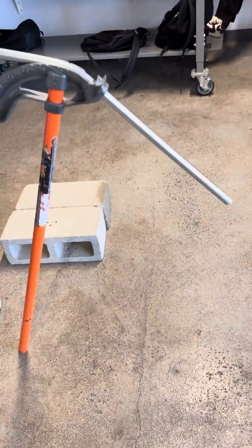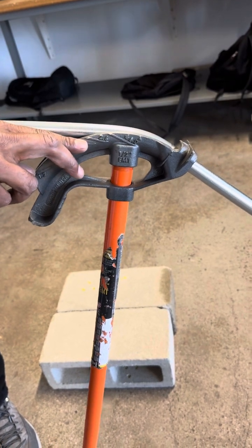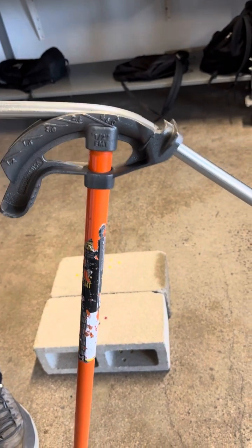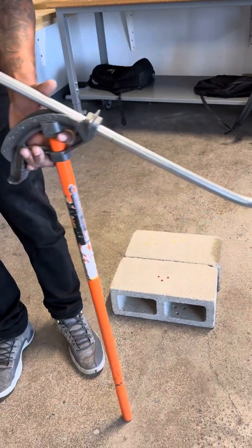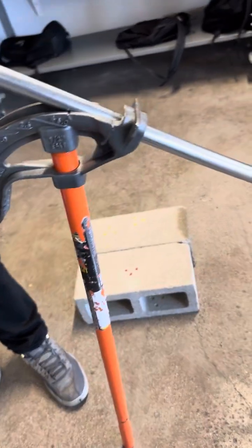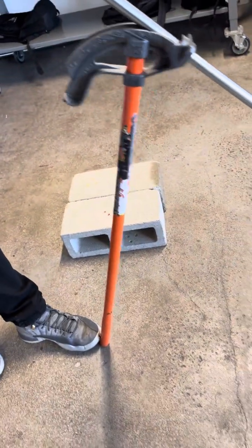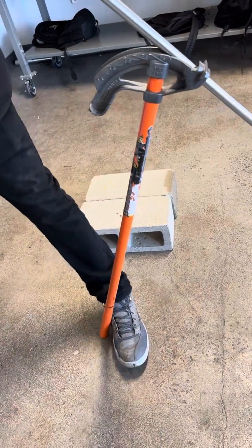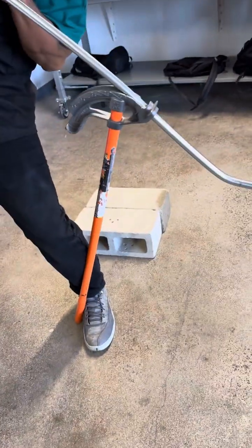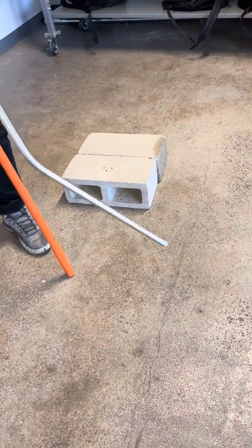And as you can see, I didn't take it all the way inside the bender. I laid the bottom of the pipe on the 2.0 mark, which is the multiplier for 30 degree, okay? You would take the pipe out, you rotate it, all right? Once you rotate it, you find your second mark, and you line it right back up with the bend mark. Make sure you look straight down the pipe, make sure it's all the way level and straight. Same thing, lock it in place, take it down again to a 30. Right there, there you go. You have your 30-degree offset.